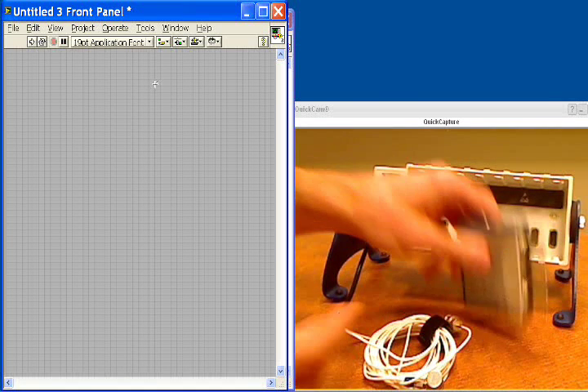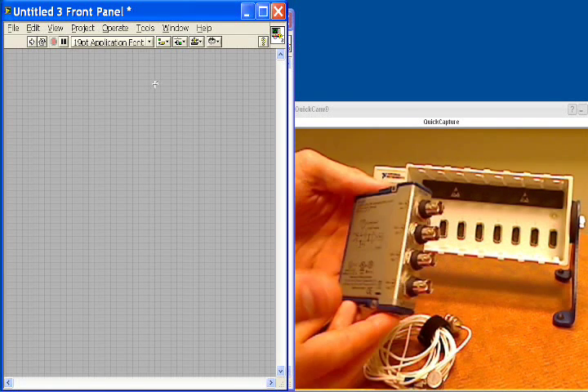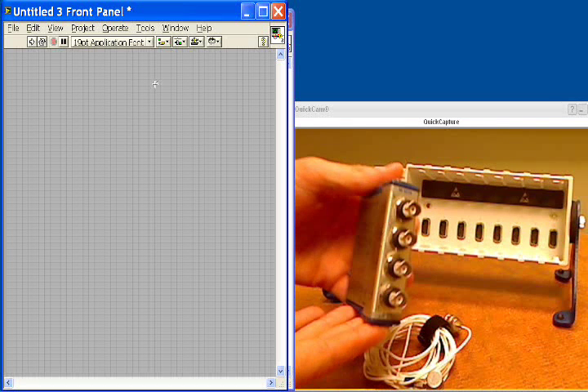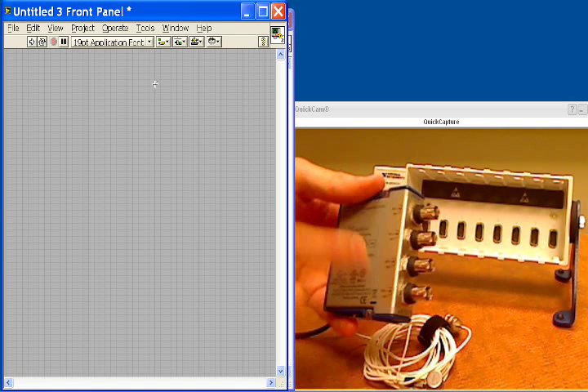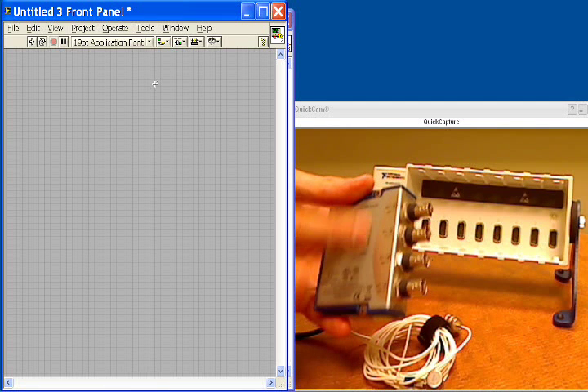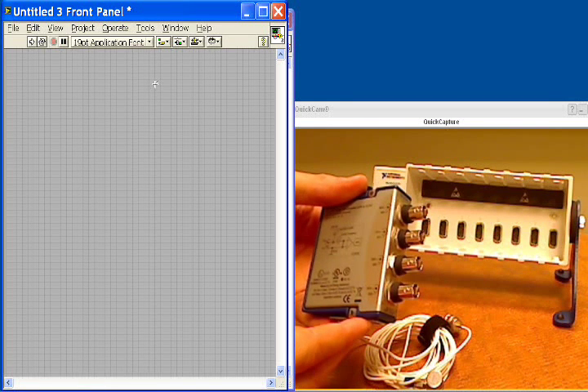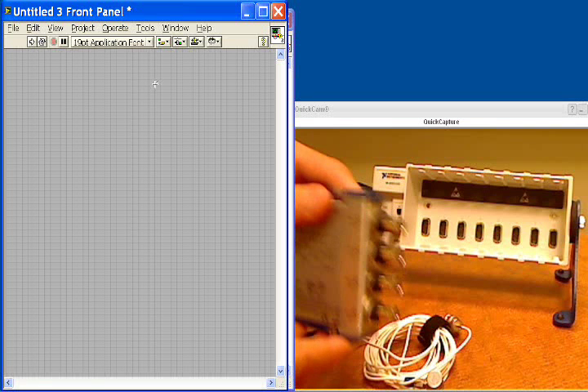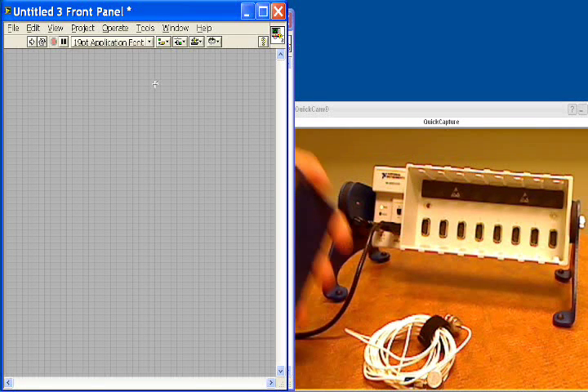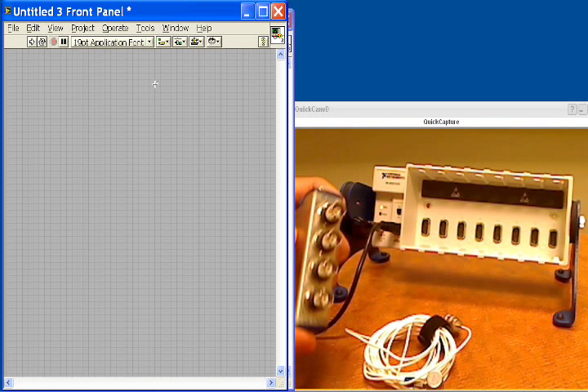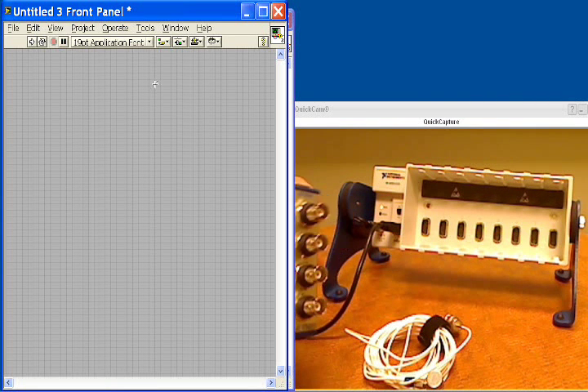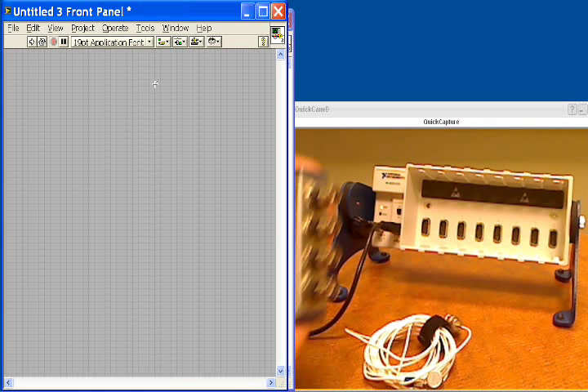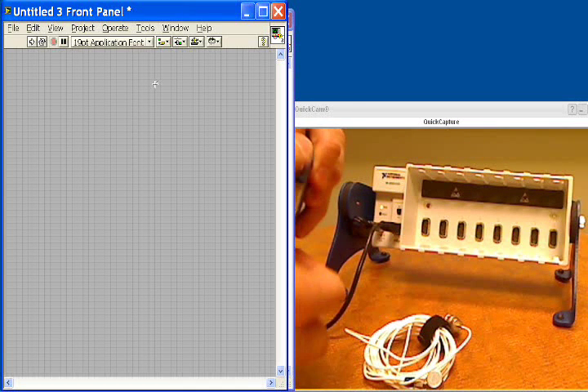For the C-Series module, we have the 9234, which is our sound and vibration module for accelerometers and microphones. It's four channels, independently sampled, 24-bit A-to-D converters, each one sampling at over 50,000 samples per second. The module also has built-in excitation to power the accelerometers and microphones, specifically known as IEPE or ICP excitation.